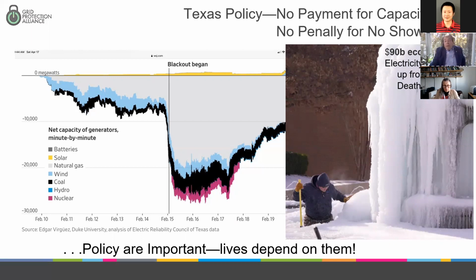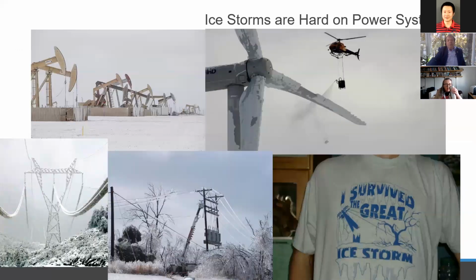Natural gas won't solidify until about minus 250 degrees, but you've got propane, butane, and more importantly, water. So wellheads freeze, and dry air will freeze. If you don't have heaters on the pneumatic lines, even at 3,000 PSI, you'll have moisture in that air and the orifices will freeze.